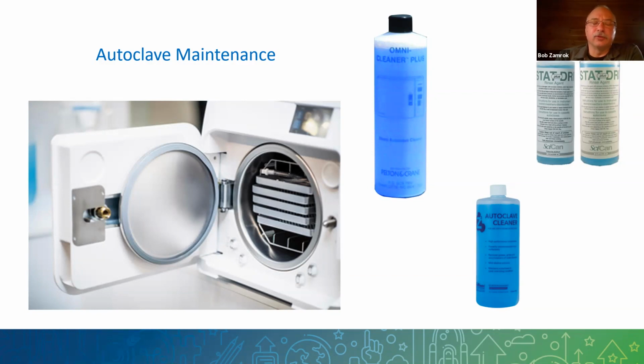When running a steam sterilizer like this one, it dumps water inside the chamber, boils it, and expels some of the steam periodically. Then it regenerates that water back into a reservoir and uses it again. So you want everything clean in there and avoid bringing impurities into that water - that's why you'd drain it once a week, to get rid of that stuff.